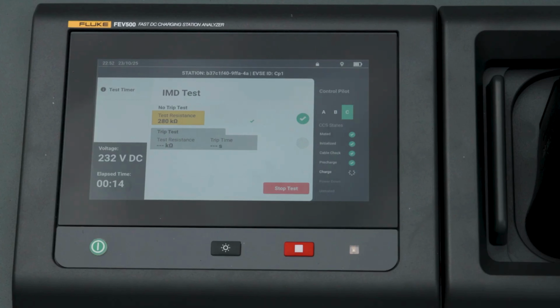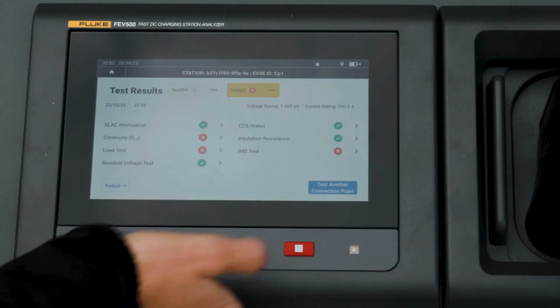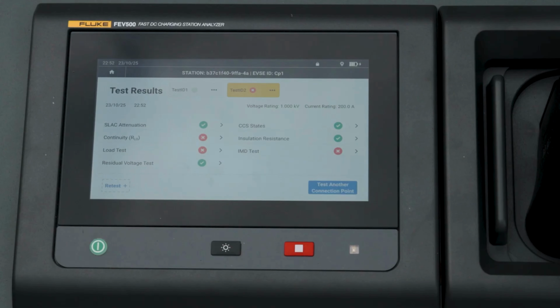So what was happening there, we were performing a no trip and a trip test essentially. And because we didn't have an IMD, it showed yes, it passed on the no trip test because nothing was tripping. But since it didn't have the IMD, we weren't able to trip anything, which was showing a failure on the trip test. And then the last measurement that happens kind of simultaneously with the IMD trip test is a residual voltage test. And I'll talk about that in just a second here.